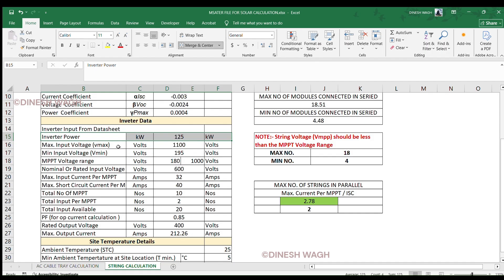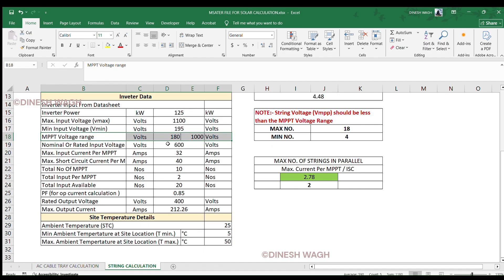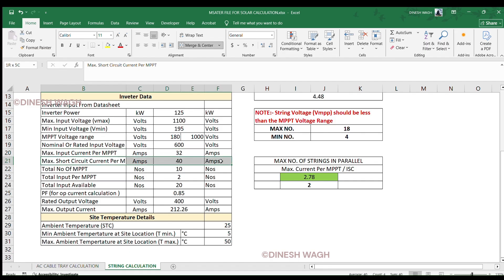The inverter specifications are: maximum input voltage 1100 V, minimum input voltage 195 V, MPPT range 180 V to 1000 V, maximum current per MPPT 32 A, short circuit current per MPPT 40 A. Number of MPPTs available is 10, with 2 inputs per MPPT, meaning 20 inputs total. We must ensure our PV array fits well within this limit.